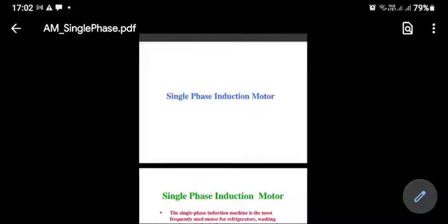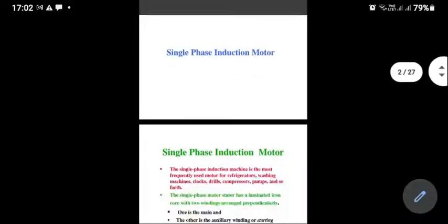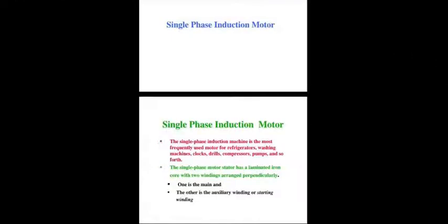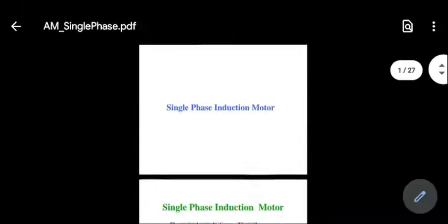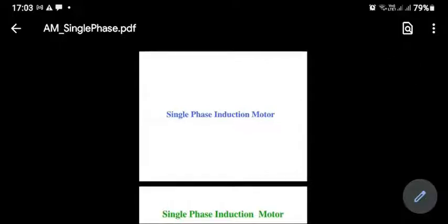No rotating flux. And as I had mentioned in the previous lecture, the flux that is produced by the single phase winding on the stator alternates polarity continuously. North pole becomes south and south becomes north continuously at the frequency of the supply. That flux, although it's not rotating, in theory it can be thought of as the algebraic sum of two oppositely rotating equally strong fluxes.